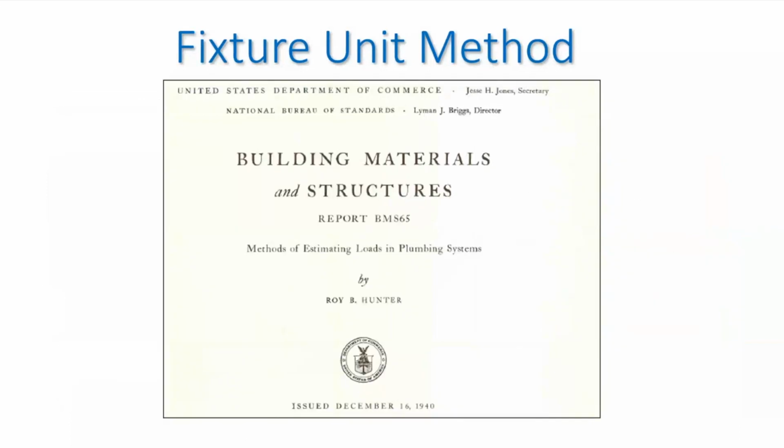If you really want to go into detail on how that curve was designed and what engineering assumptions Roy Hunter used, this is the document to go to. It's still published by the American Society of Plumbing Engineers. It goes into great detail on how the design curve was created, the binomial model he used, how he weighted and combined the curves, and how he derived the fixture unit values. All of this is in great detail in this document.